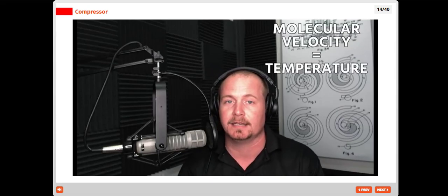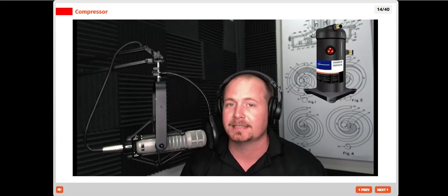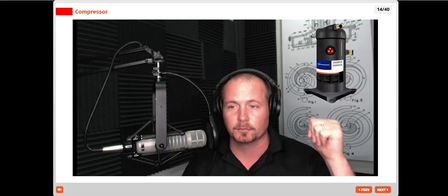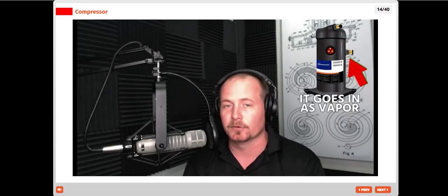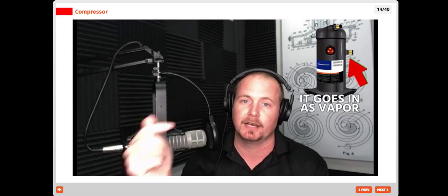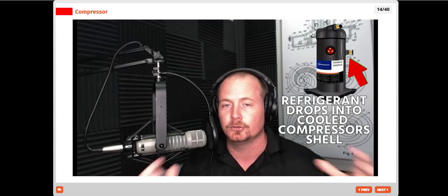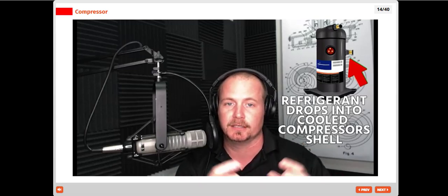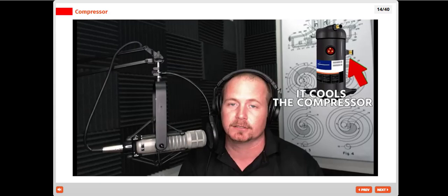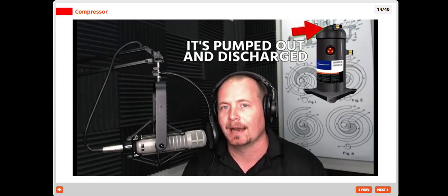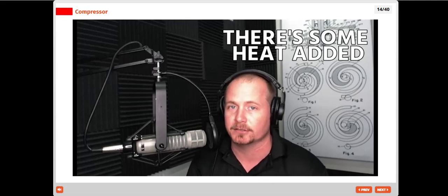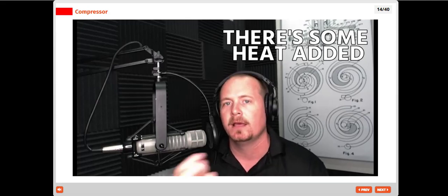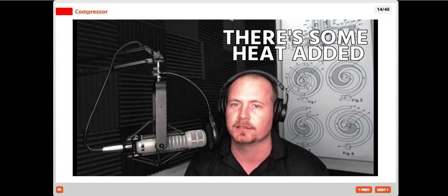And if you think of this scroll compressor behind my shoulder here, it goes in as vapor. In fact, how it really works inside of a compressor is that the suction line refrigerant drops into a refrigerant-cooled compressor's shell. It cools the compressor, mixes with the oil, and then it's pumped out into the head where it's discharged. And so there is some heat added from the compressor itself, from the windings and from the different parts inside there with the friction, the bearings and all that.